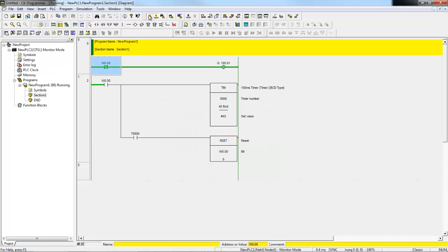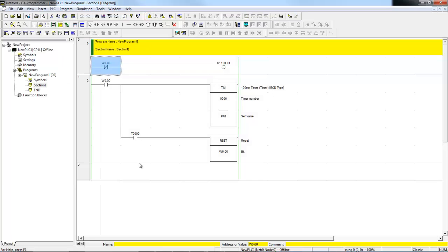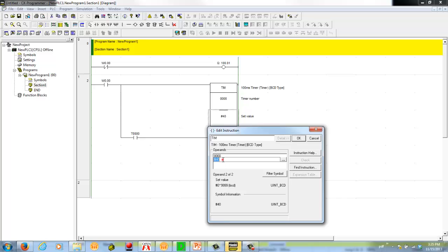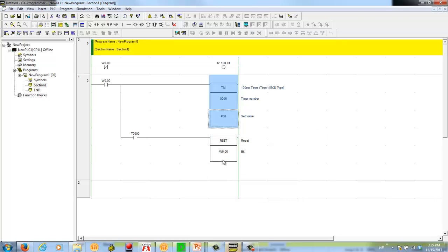So let's make a quick change to this program. I'm going to get offline to do that. Notice when you're offline, the screen is white. That indicates that you can edit, and when you get online, the screen is gray. That means that you cannot edit. I'm going to do something simple. I'm going to change this timer set value. I'm going to change it from 4 seconds to 5 seconds.